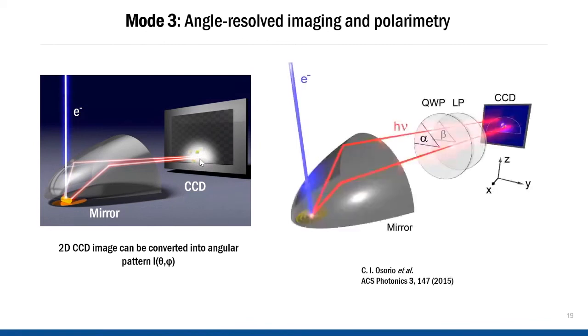Now, the third imaging mode is the angle-resolved imaging mode. On the Spark, angle-resolved imaging is performed using a 2D CCD camera and a slit. Every point on the camera image corresponds to one angle of emission. So every point in this image represents a unique angle of emission. With this 2D image, we measure the whole angular profile in one go, and you can do this with or without a color filter. We can also do polarimetry in combination with angle-resolved imaging. For any emitter, the light that's emitted along different angles could have very different polarizations. So an average measurement may not always be enough, and doing polarimetry in the angle-resolved mode can be very valuable. You can find out the optical modes available, determine the degree of polarization of the source, and you can study chirality, which is quite hard to do.